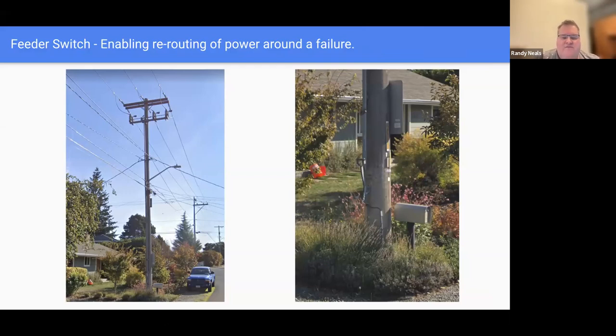If you have a ring with 4 or 5 switches around it, you can restore power more quickly, because a person just has to drive up to where this handle is on the pole, unlock it, and either close it or open it as needed. Really modern electrical grids will even have electric motors that drive this with little battery systems on the pole, using the same kind of radio technologies we talked about with smart meters to control these switches. The advantage is speed. A central control operator, for example at Seattle City Light, could look at the system, identify where the fault is, and through a couple of computer commands open and close switches to isolate where that tree fell on the wire, restoring service to a commercial district or hospital much more quickly. In Seattle, we find those types of things in the downtown core, where service to an individual building is very critical because thousands of people depend on it, so there's more automation in those bigger areas.